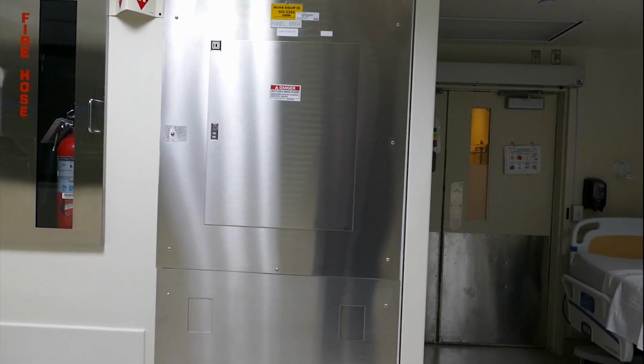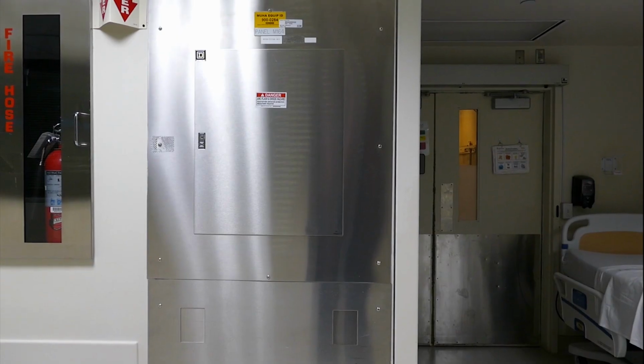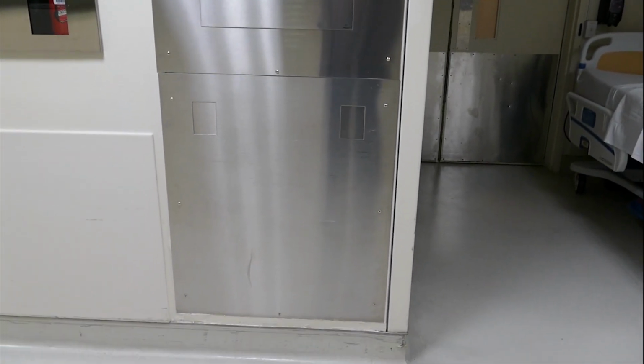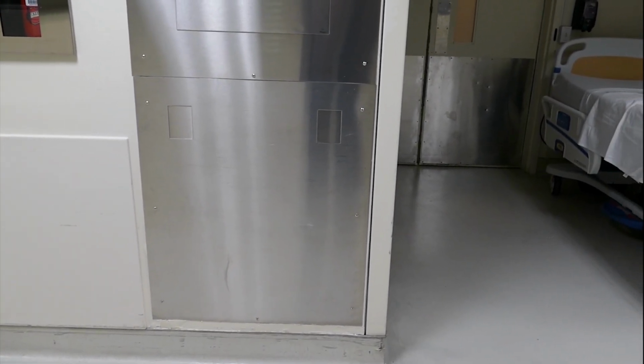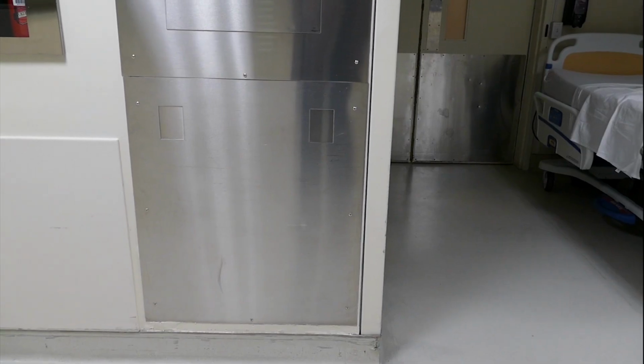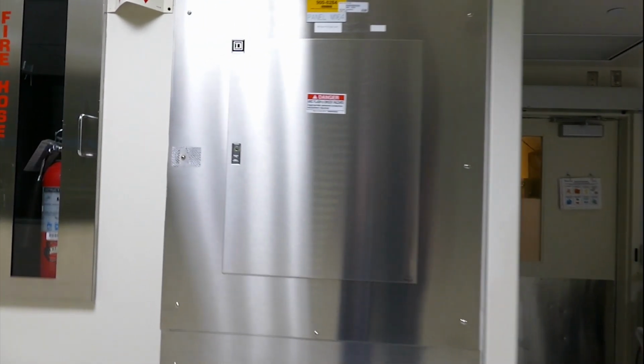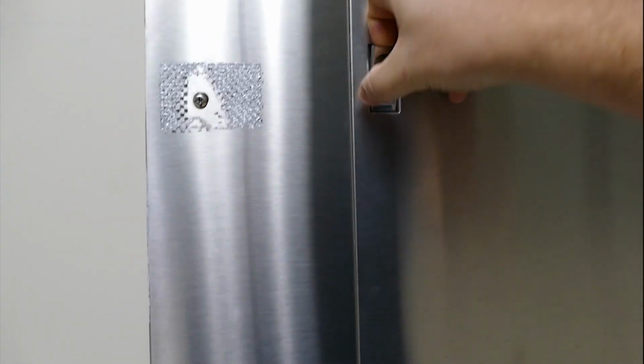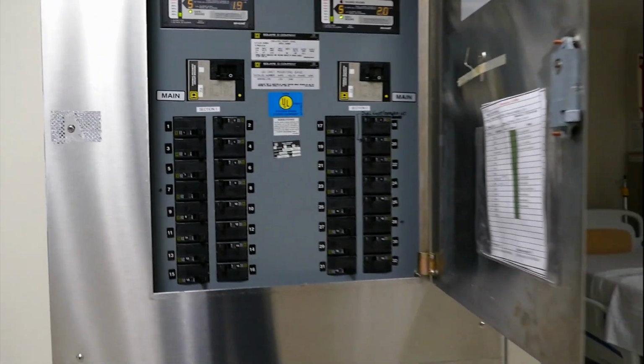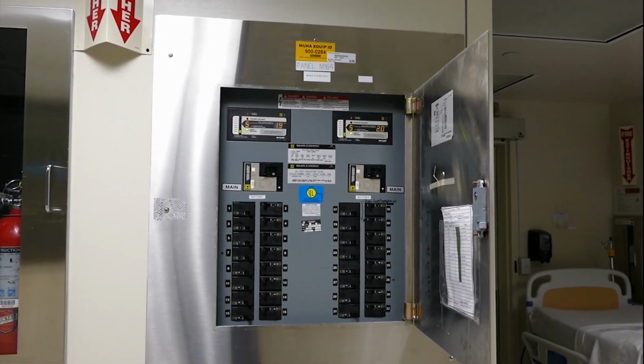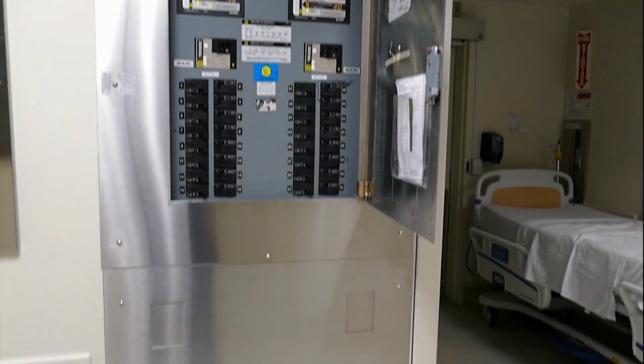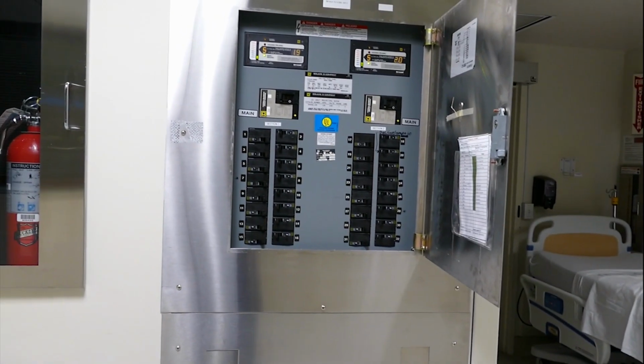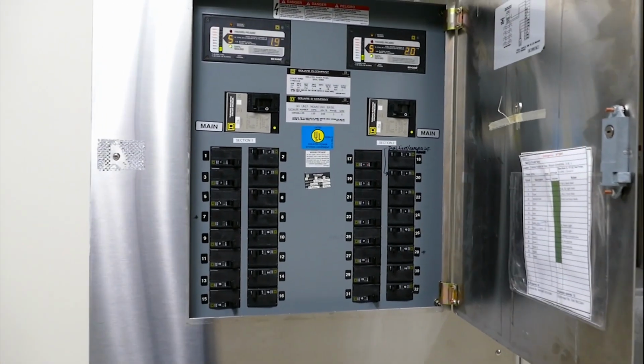This is the LIM panel. That's the line isolation monitor panel. Down here is your line isolation transformer. There actually are two transformers because behind the panel, you can see we have two separate panels. So there's two transformers down there, and the secondaries feed up here.